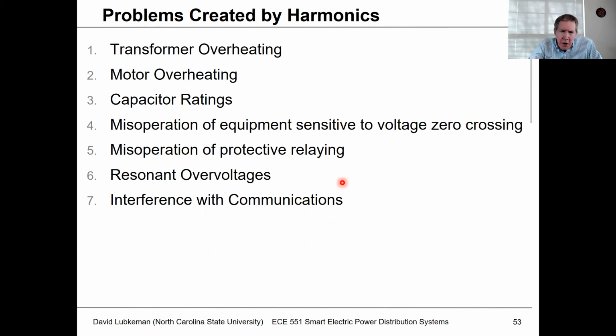So why are we concerned about it? Well, if you have a load that's producing harmonic currents and you connect that up to a transformer, then you're going to get additional heating. What this does is it adds to the RMS current, and so you're going to get more I²R losses. If you get harmonics in the voltage, that results in more core losses. And so this could cause transformers to overheat.